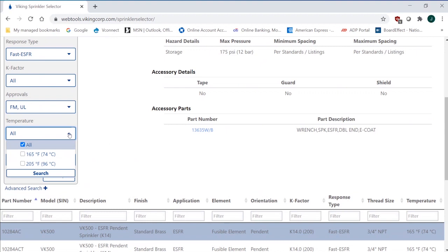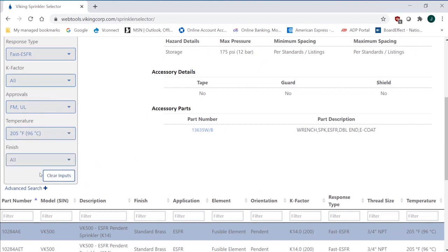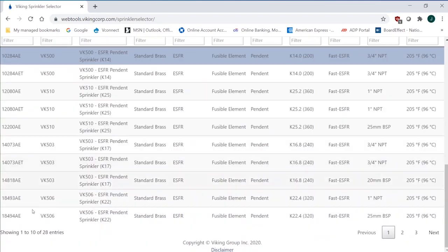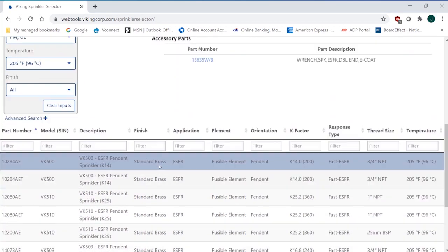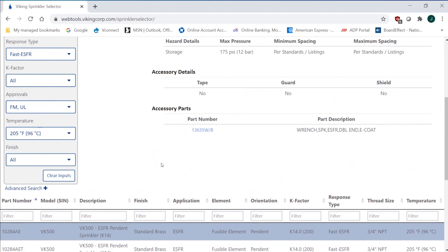Again, on temperature, the ESFRs are either ordinary or intermediate. And again, at the top of the warehouse, if you believe that that sprinkler is going to get above 100 degrees, not only we, but the NFPA 13 requires you to use intermediate temperature. So if you use intermediate temperature, again, we're down to 28 entries because that's the 200-degree operating elements.